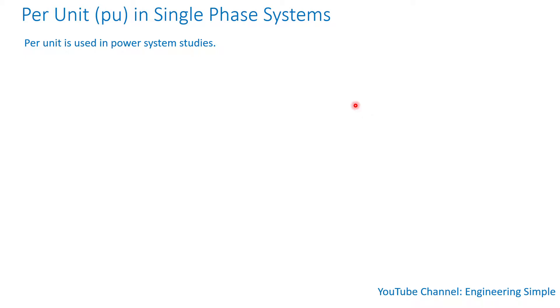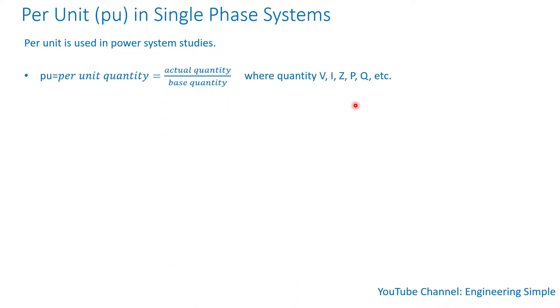Per unit is used in power system studies. Instead of using actual units like MVA, KVA, voltage, amps, or ohms, a base is used across all quantities and everything is converted on that base — voltage, MVA, impedance, and so on. The per unit quantity is basically the actual quantity divided by the base quantity. The actual quantities can be measurements, test information, or design information — voltage, current, impedance, real power in watts, kilowatts, or megawatts.